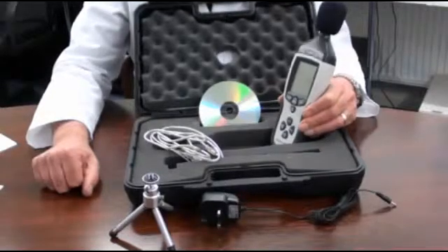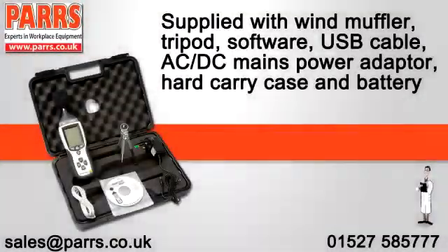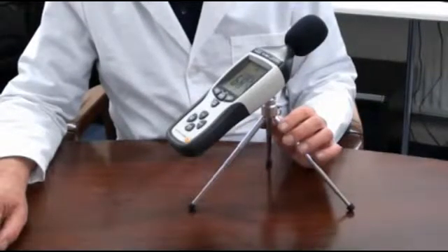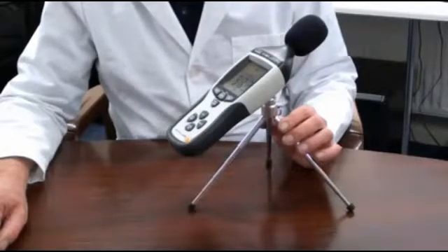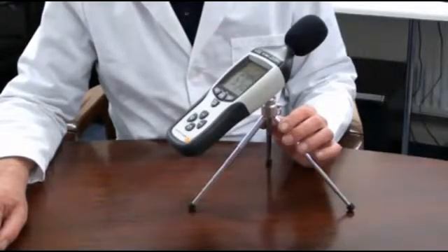It also has a standard 1/4 inch camera bush for tripod mounting. It has a measurement capability of up to 130 decibels with user-selectable A or C frequency weightings. It also features slow or fast response filters, data hold, a minimum maximum memory, peak maximum and peak minimum.